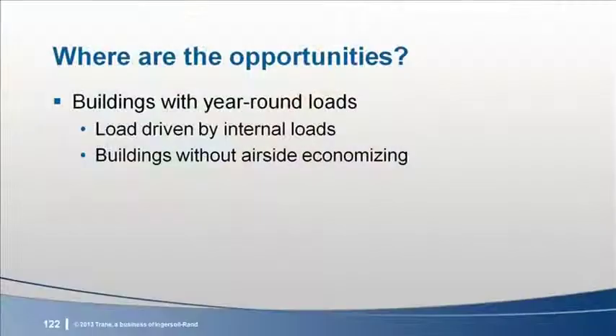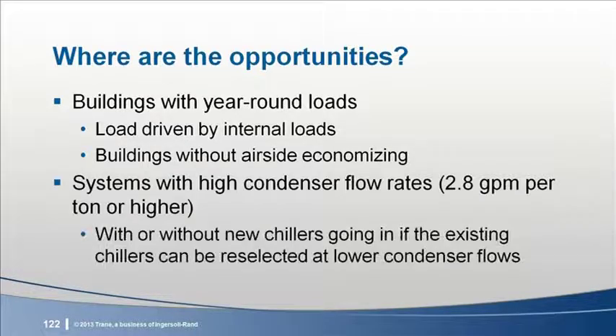So what are you looking for in an application? Where are the opportunities? The first one is to find an application with a lot of year-round load. This could be an application that is driven by a high amount of internal loads, or one that doesn't have an airside economizer to remove the loads when it's cold outside. Another potential candidate is an existing system with a high condenser flow rate, which I consider to be systems that have 2.8 GPM per ton on the condenser flow or higher.